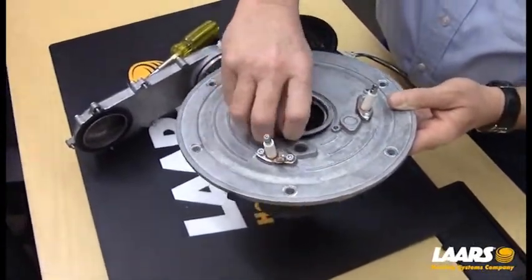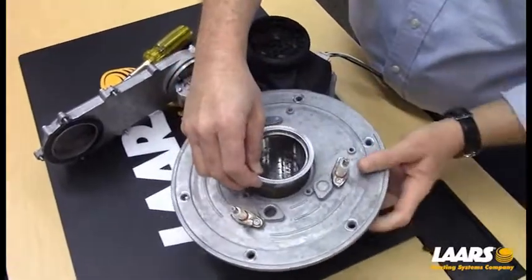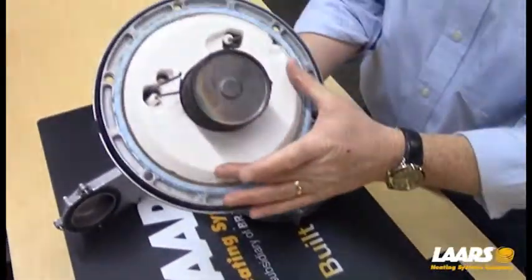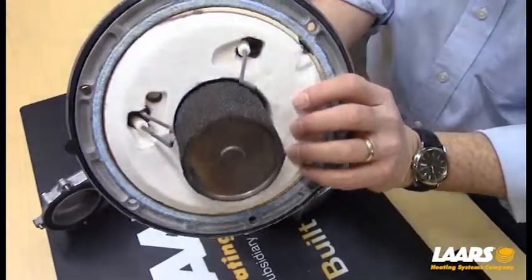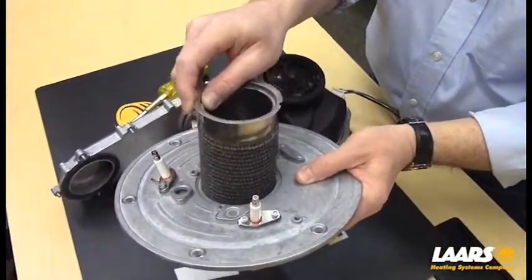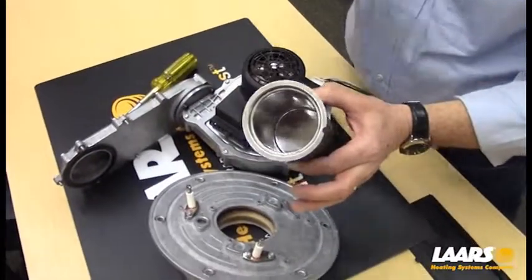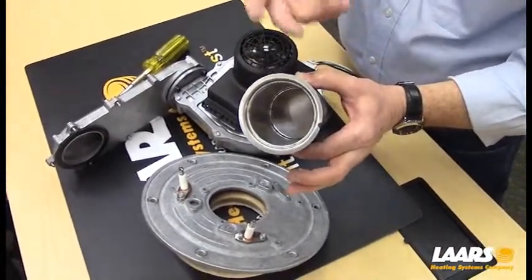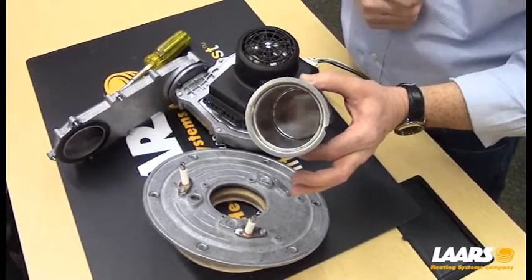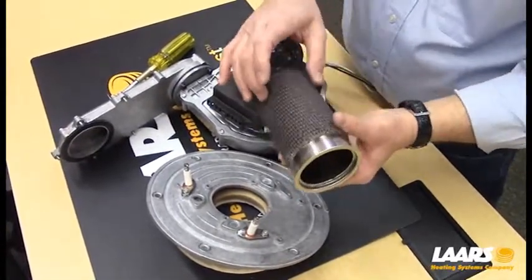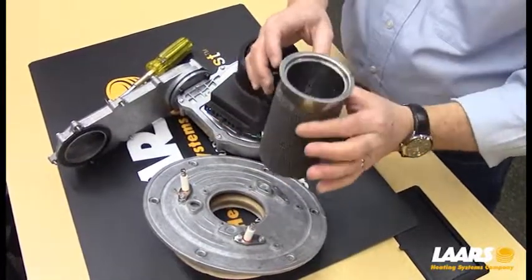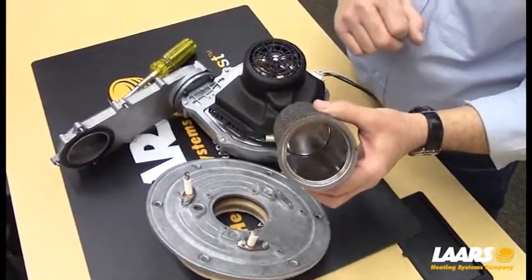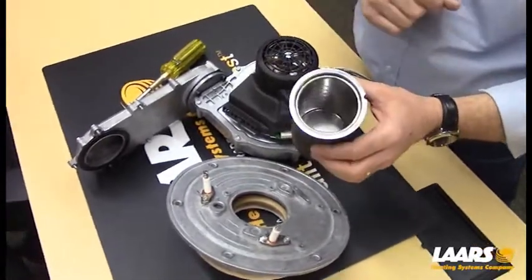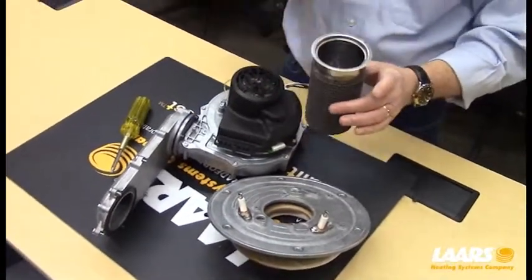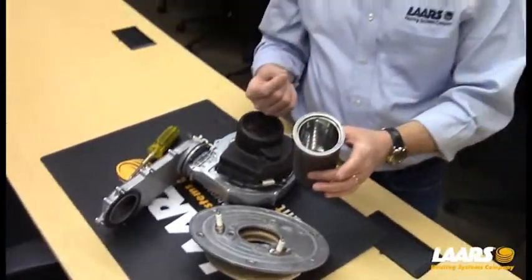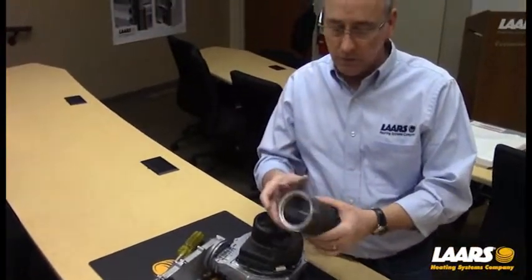Gently slide this burner out of position, because on the back side is a refractory block. You don't want to distort this or destroy it. So gently bring this out of position. Now you can inspect the inside of the burner for bugs, debris, grass clippings, anything that may have gotten drawn into the actual burner, and the mesh itself. If it does need to be cleaned, hit it with an air compressor. Blow it out. You can use warm water and just rinse this in warm water. However, if you have sheetrock dust due to new construction, you don't want to be putting this into warm water with sheetrock dust.